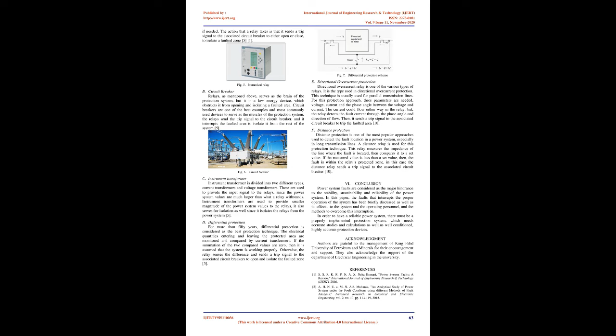C. Instrument transformer. Instrument transformers are divided into two different types, current transformers and voltage transformers. These are used to provide the input signal to the relays, since the power system values are much larger than what a relay can withstand. Instrument transformers provide smaller magnitudes of the power system values to the relays. They also serve for isolation, since they isolate the relays from the power system.